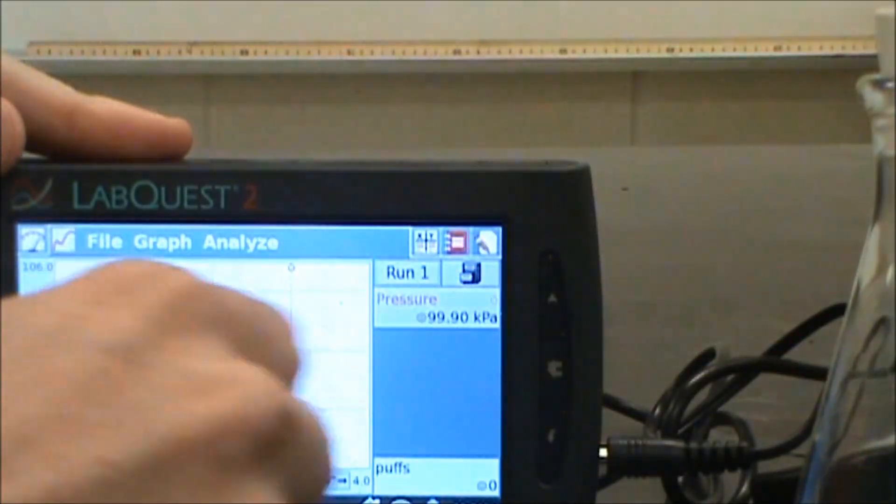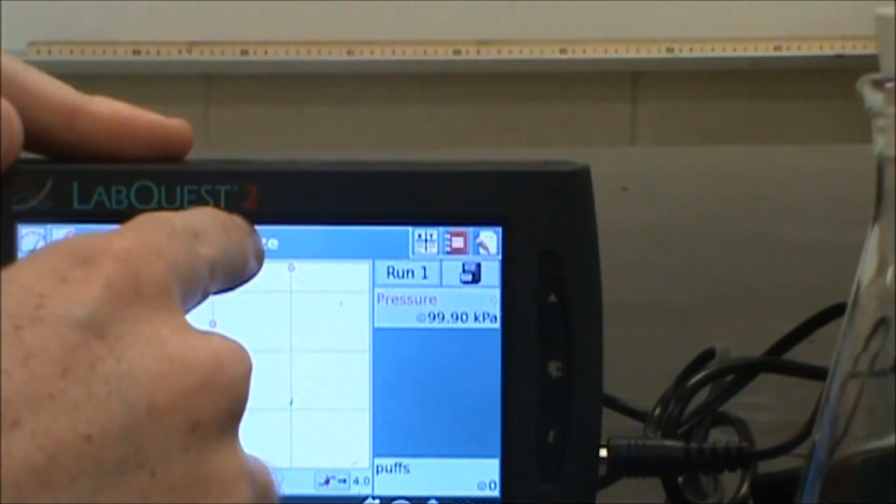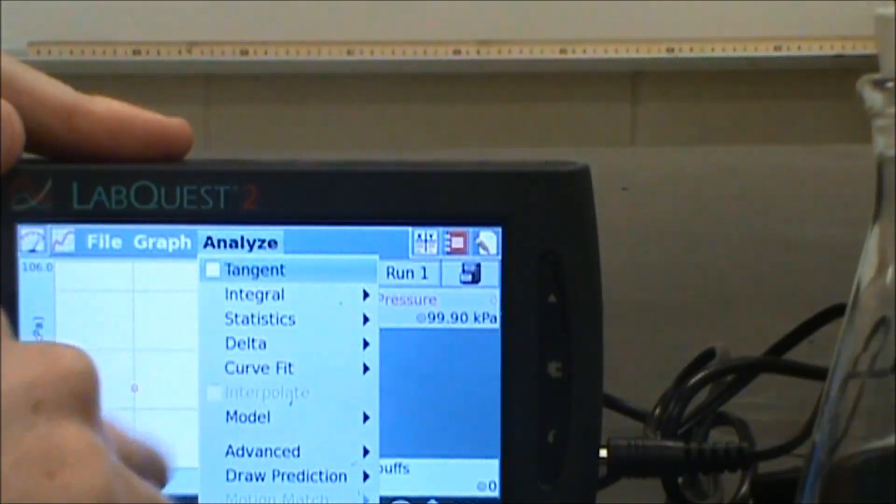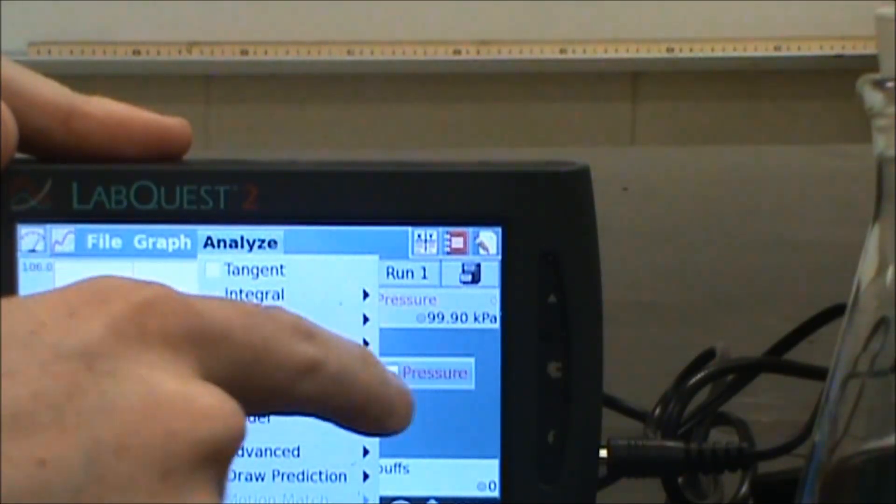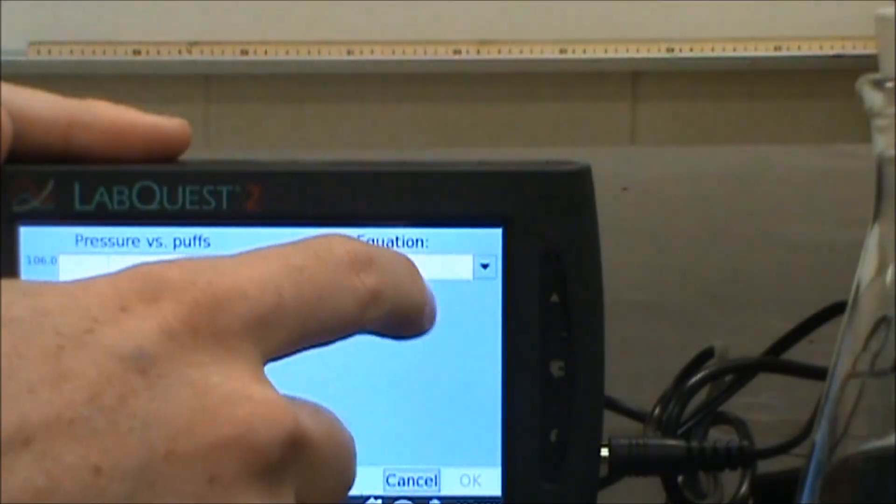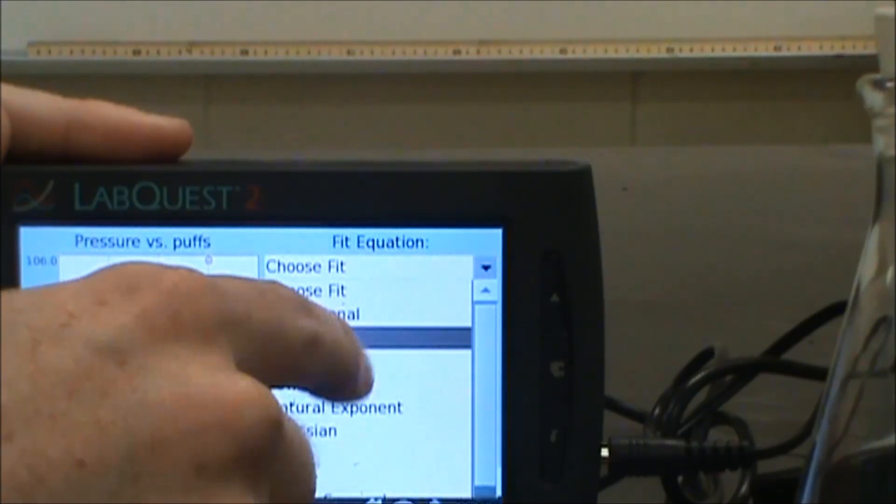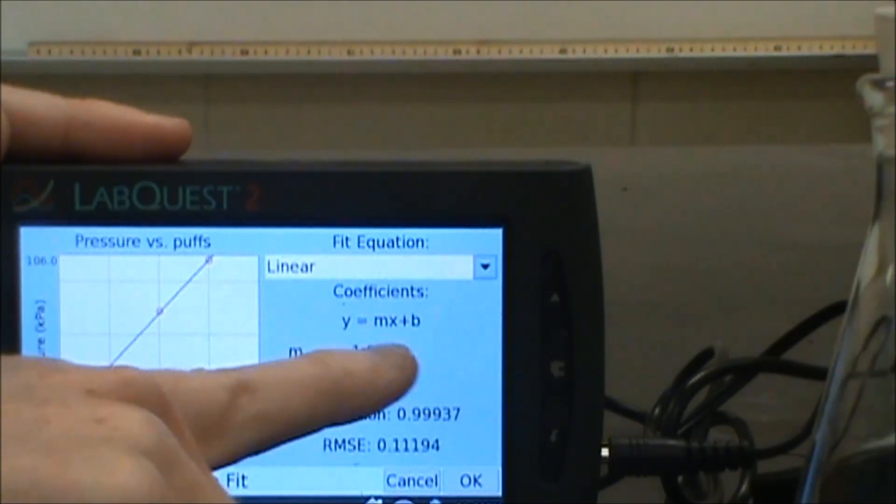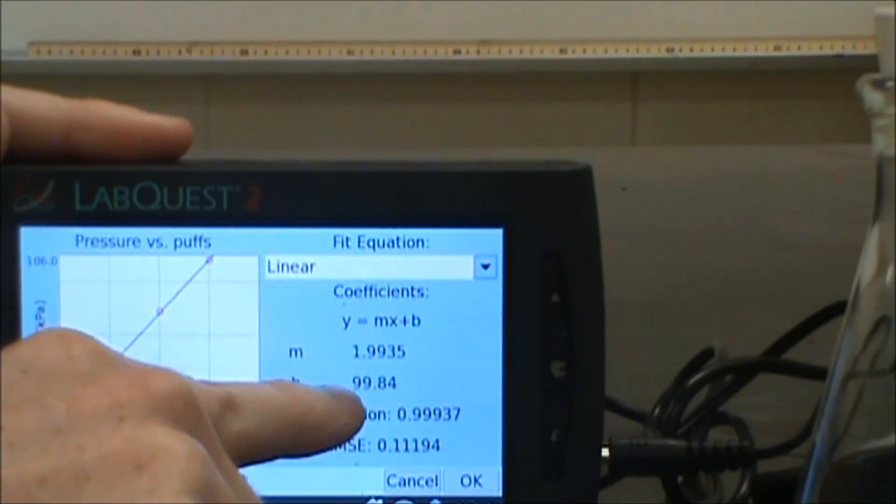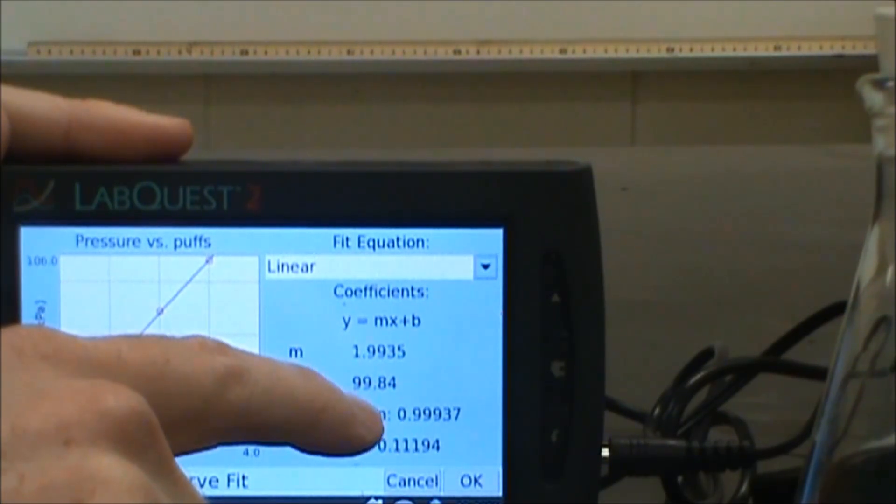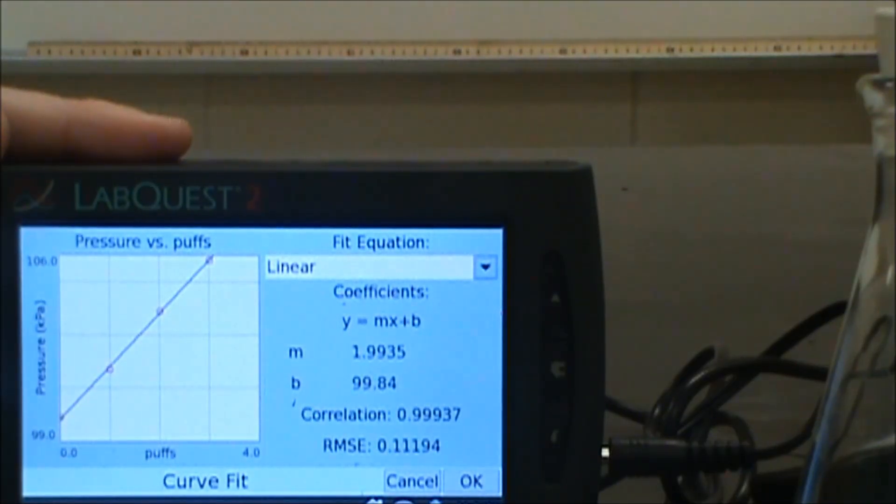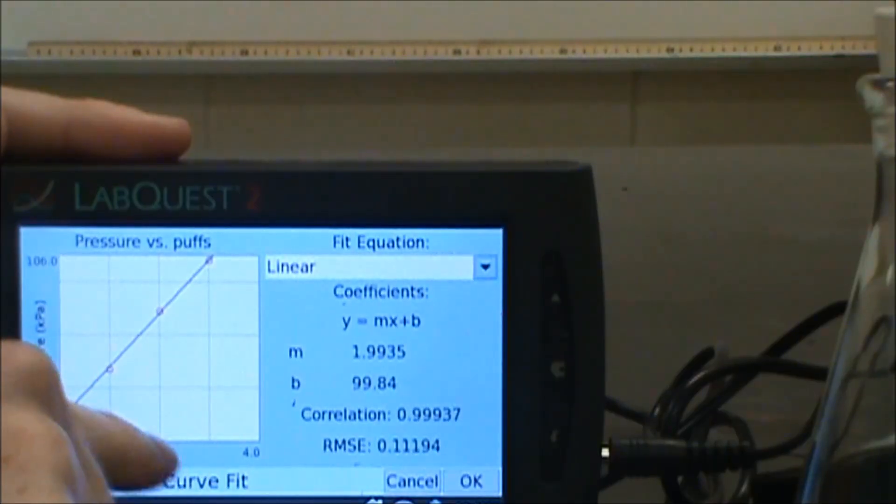I'm going to stop there. You can continue on, although eventually this may pop out from having so much pressure. I can go to analyze. Where it says curve fit, I can select my pressure. Then I can choose a line of best fit. For this one, I'm going to choose linear. It gives me a y equals mx plus b. My slope is 1.9935. My intercept, 99.84. That gives me my line of best fit for puffs of air versus pressure.